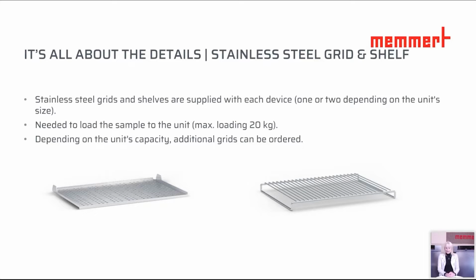And here we have in standard for the Eco 50 one shelf for the size 105. We have two for size 150, 240 also two. And we can add additional shelves here also in CO2 incubators. The maximum is 5 shelves which could be included for size 105, 6 for 150, and for 240 we can place in 12 of these shelves.